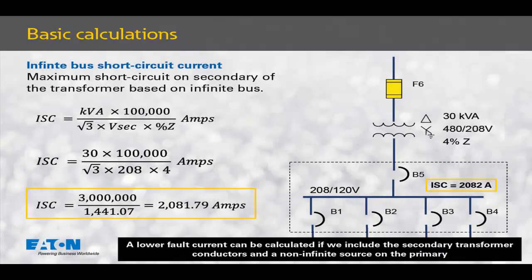The next calculation we need to make is the short circuit current on the primary. To get this number, we'll calculate the secondary infinite bus short circuit current and reflect that to the primary. Putting our math to work for infinite bus short circuit current calculations, we calculate 2,081.79 amps on the secondary, which we'll round up to 2,082 amps. This is based on a 30 kVA transformer with 4% impedance.